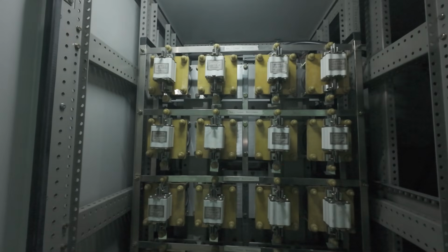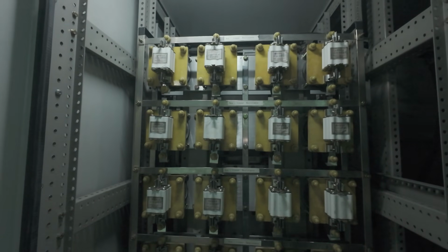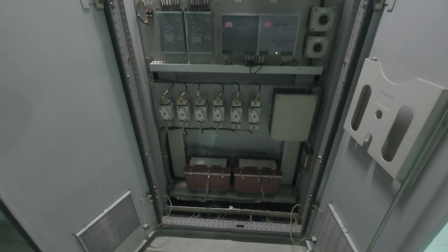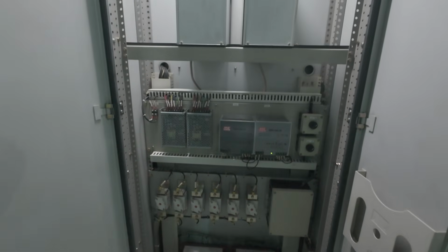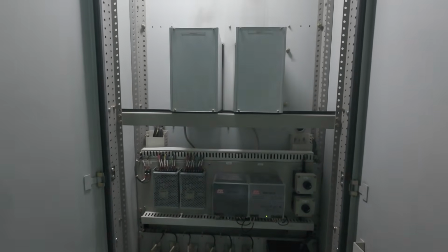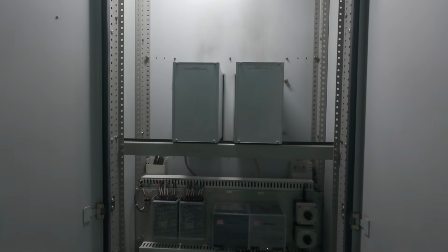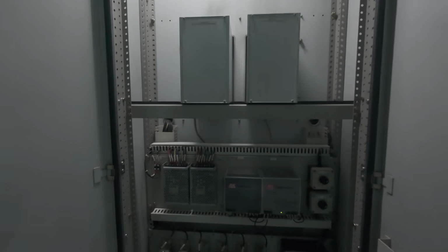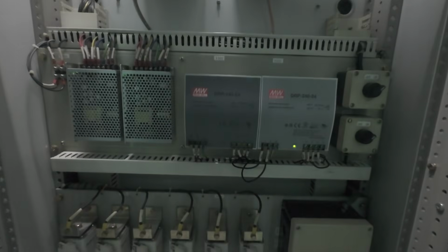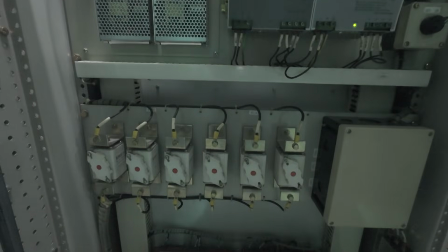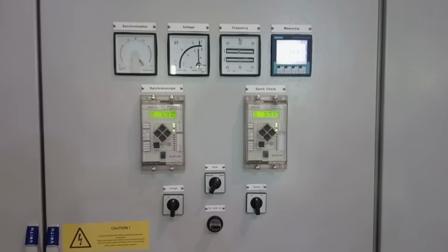Now the excitation transformer has power. The thyristor system wakes up. The AVR becomes active, and the generator begins exciting itself. At that exact moment, the machine becomes electrically alive. But even now, the generator still cannot connect to the grid because the electrical grid is brutally strict.